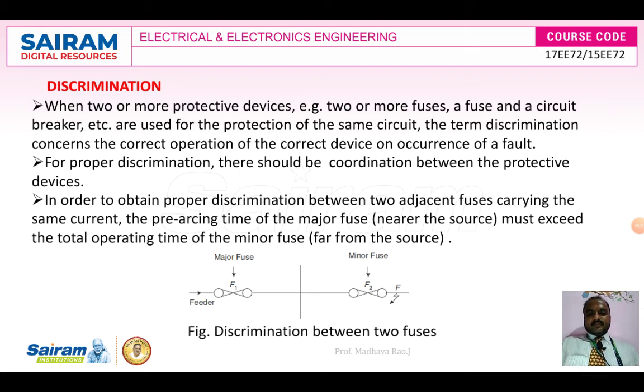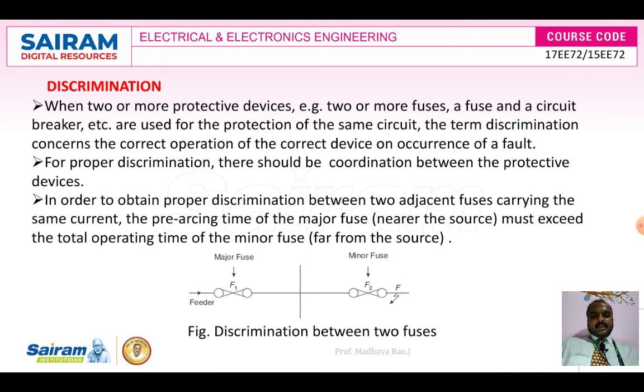In order to obtain proper discrimination between two adjacent fuses carrying the same current, the pre-arcing time of the major fuse near the source must exceed the total operation time of the minor fuse. That is very important — the minor fuse must melt first. If the minor fuse does not melt, then the major fuse must melt. This is called discrimination.